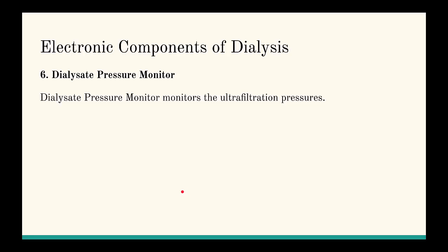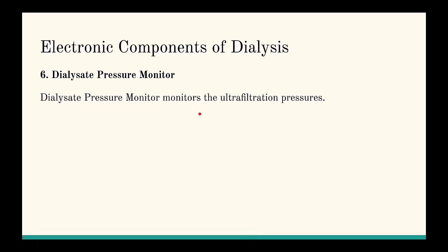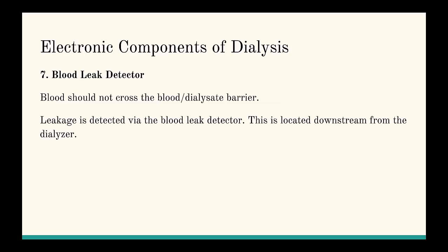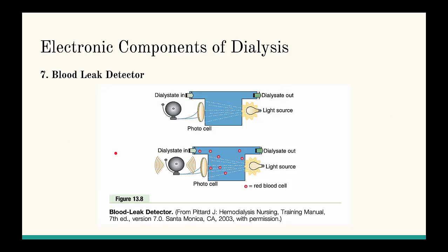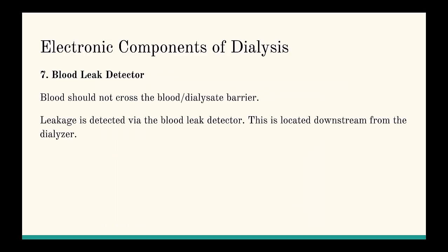Well, we also have this other pressure monitor, which we will not go into detail, but we still thought that it would be appropriate for you to know that we also check the pressure in the filtration procedure. Dialysate pressure monitor monitors the ultrafiltration pressures. These are inside the filter that we talked about before. We also have this other thing which is called blood leak detector. As you remember from the earlier slides, we have this synthetic porous membrane that's actually doing the filtering, and it would have blood on one side and the dialysate solution on the other side.